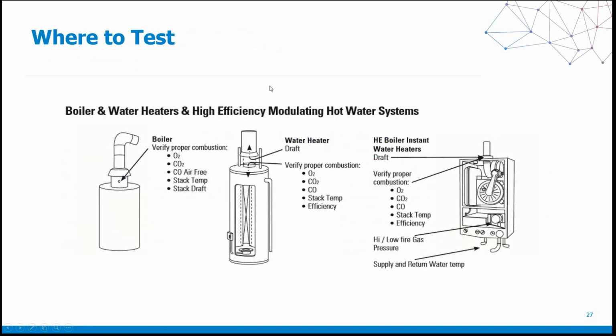Where to test? We have a host of different systems here. We have your solid fuel boiler with the draft hood here. We want to check for both draft and combustion right in this spot, underneath that draft hood. For a water heater, notice I have two things here. First, I want you to check for draft as we go up in here, so you put your probe in here and check for draft. Then I want you to verify your combustion parameters down in here as we angle down toward the tank. So for water heaters, we have these two different spots we should be testing.